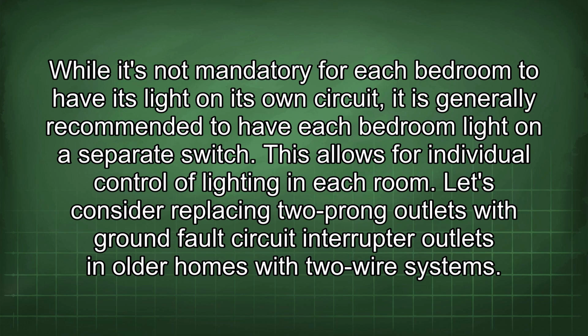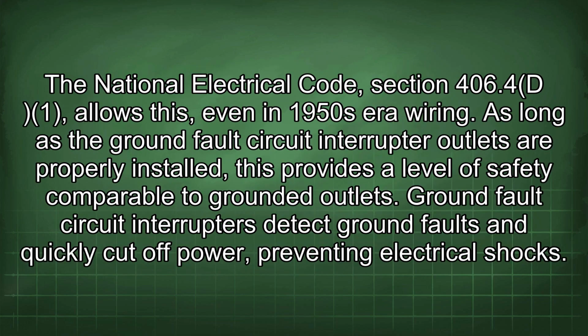Let's consider replacing two-prong outlets with ground fault circuit interrupter outlets in older homes with two-wire systems. The National Electrical Code, Section 406.4(D), allows this, even in 1950s era wiring. As long as the ground fault circuit interrupter outlets are properly installed, this provides a level of safety comparable to grounded outlets. Ground fault circuit interrupters detect ground faults and quickly cut off power, preventing electrical shocks.